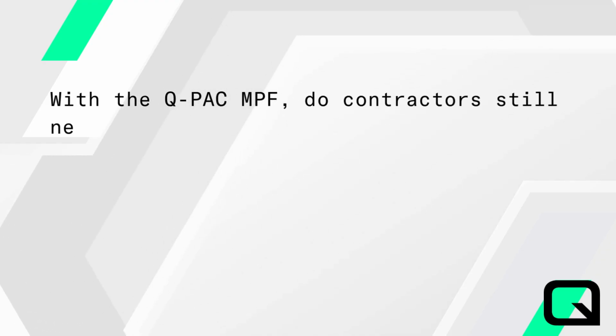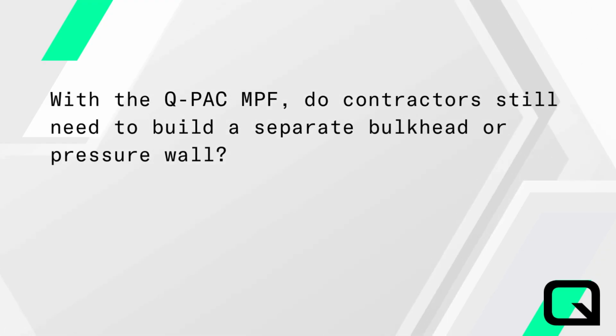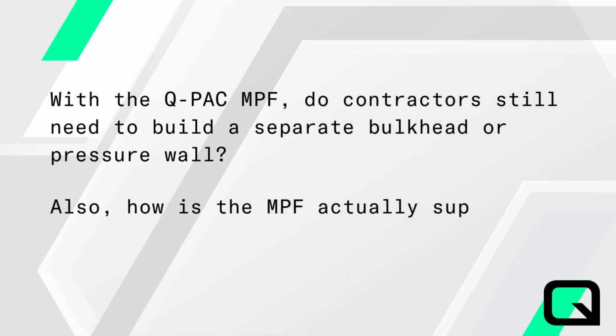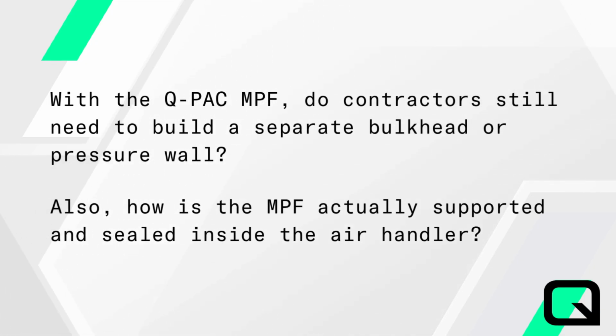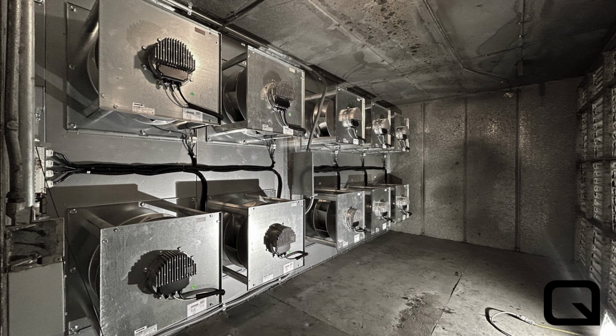With the Q-PAC MPF, do contractors still need to build a separate bulkhead or pressure wall? And how is the MPF actually supported and sealed inside the air handler? So there might be cases where an air handler isn't totally square or where the ordered MPF frame is smaller than the total cross section. In these cases, a field fabricated bulkhead wall may be required.